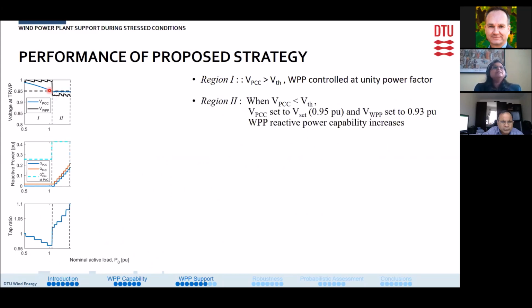Next, the PCC voltage goes below the threshold voltage, and our enhanced proposed control strategy is activated. What it does is set the PCC voltage set point equal to the threshold voltage, and the wind power plant voltage set point is changed to 0.93 according to the reactive power capability and voltage relation shown in the previous slide. With this, we see that the reactive power capability increases here.